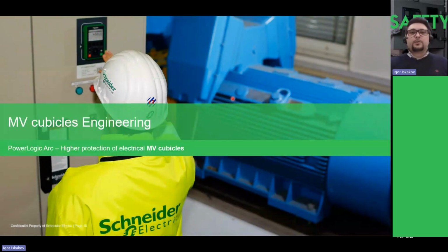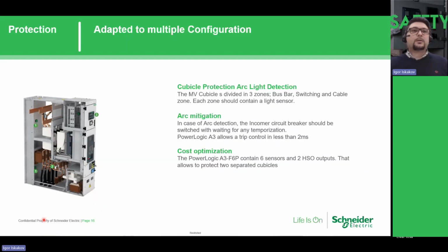So now I would like to check with you a typical medium voltage switchgear application using the A3 arc flash protection. Here is one bay of the switchgear. We have the cable compartment, which is separated, and the circuit breaker compartment, which is also separate from all the sources, and we have the bus bar compartment. Using this three-compartment switchgear, we can build fully selective arc flash protection.